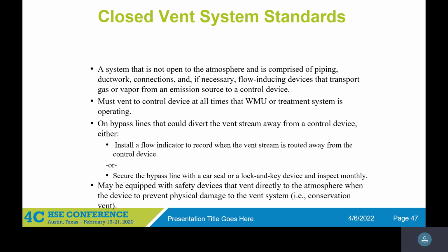Oh, then the closed-vent systems, if you have any tank or anything like that that goes to a flare, you have to have the LDAR monitoring and make sure that all the bypass lines have a flow indicator installed to record when the stream was routed to a different location, or have a car seal lock, you know, where you have those ties when you break bypass, and then you have to monitor when bypass was broken, because during those periods it was not controlled, right?